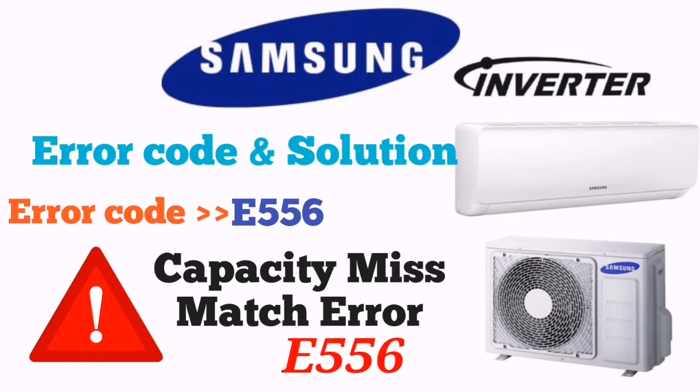If the capacity is not right, you have to change the indoor or outdoor to the exact model specification. Even if it's showing the same error, then you have to reset the option code again in your indoor unit, match the capacity of your indoor unit and download the EEPROM data. If the capacity mismatch shows again, then you have to exchange the outdoor PCB and indoor PCB and your unit will be in working condition.